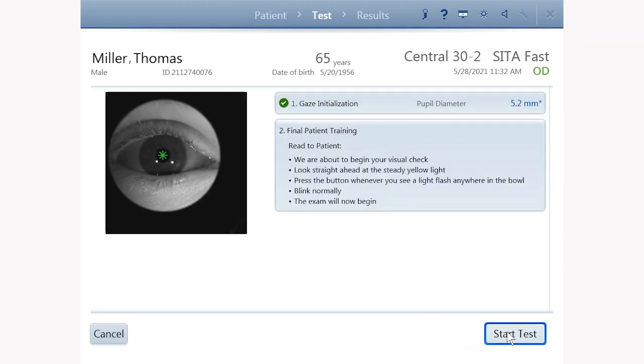If the chin rest movement is not sufficient to center the eye, you may have to make some manual adjustments. The instrument will automatically find the gaze track position and give you feedback that this has succeeded or failed. If it fails, readjust the patient, have them open their eye a little wider, and try again. If it fails after two or three adjustments, you can proceed without gaze tracking. Gaze tracking works on a very high percentage of patients.